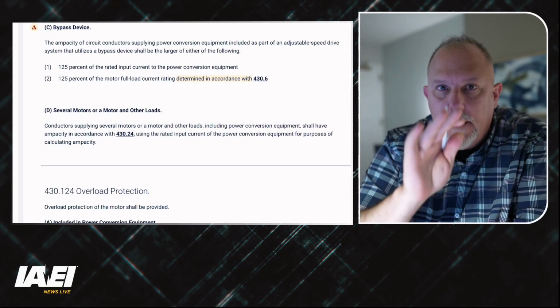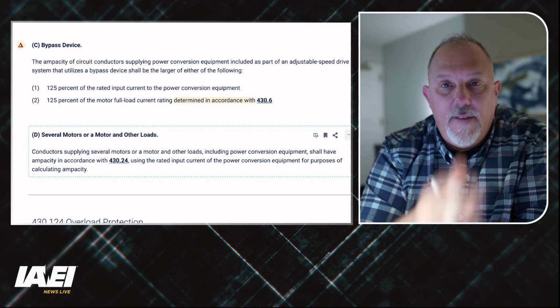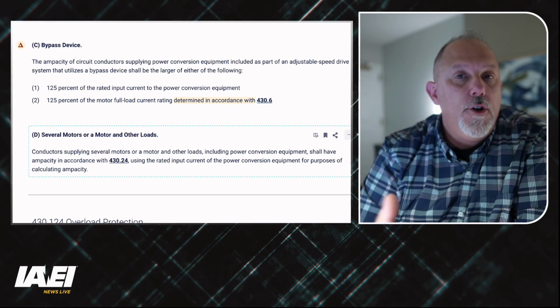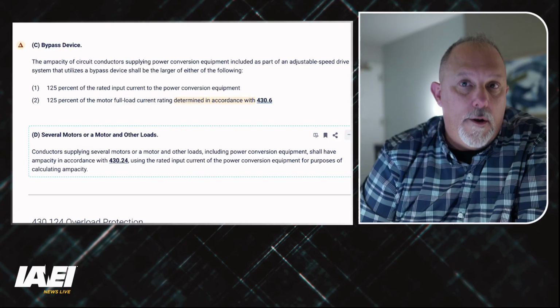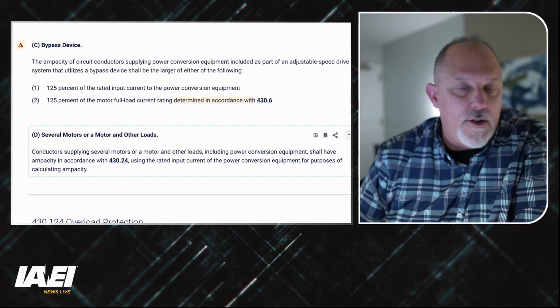But on 430.122(A), this was on the line side feeding the drive, the adjustable speed drive. Now, (C) has the bypass device. And remember, I mentioned the bypass before, and I said if you have a bypass around the drive, that means you have a means to work on the drive. So you put it in bypass, take the drive out, do whatever it is you need to do.